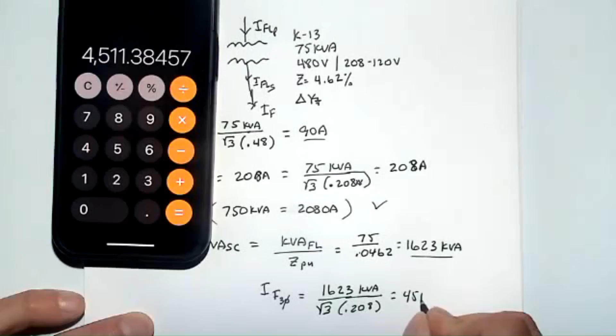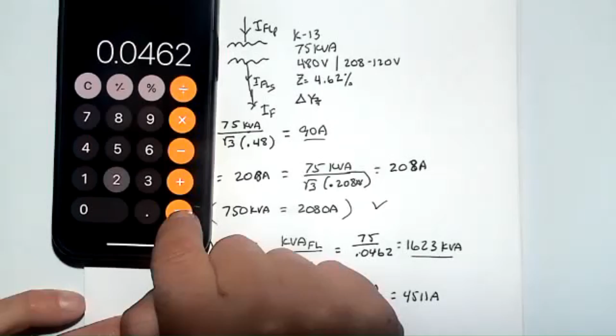And then that number, if we use our I fault three-phase, we're going to take our short circuit kVA, which is 1623 kVA, divide it by the square root of 3, and divide it by our 0.208 kV, which is 208 volts, and we end up with about 4,511 amps of fault current. If I took my number here that was 208 amps, and divide it by 0.0462, I end up with 4,502 amps, which is very close to that number. I was just off by basically the square root of 3 factor that works out in there.